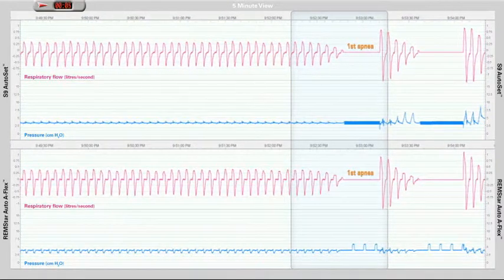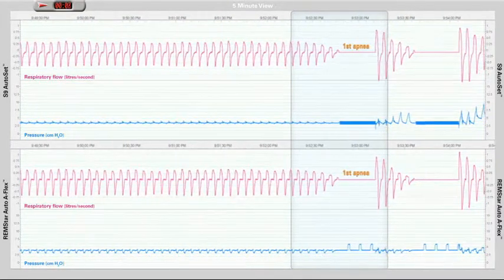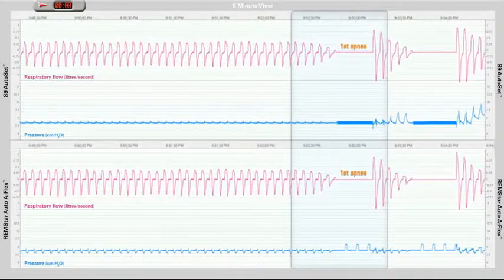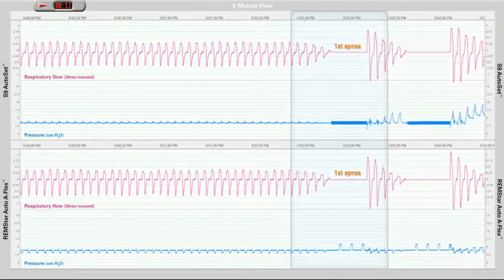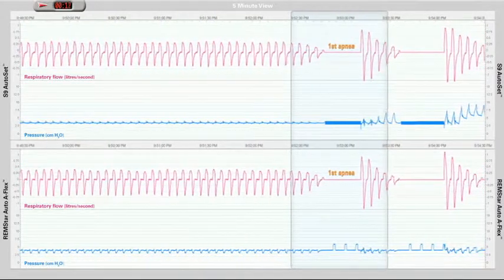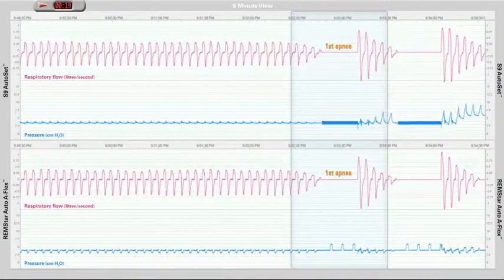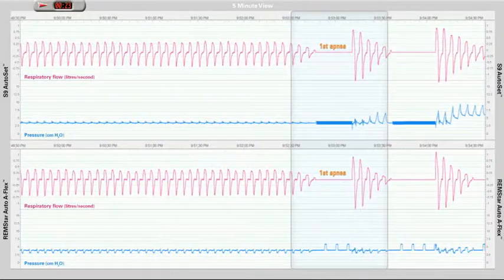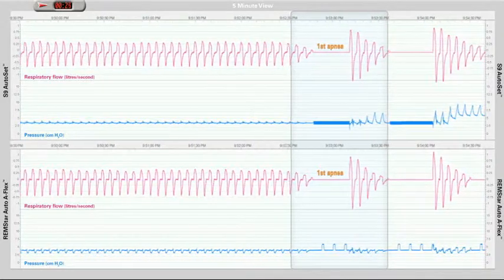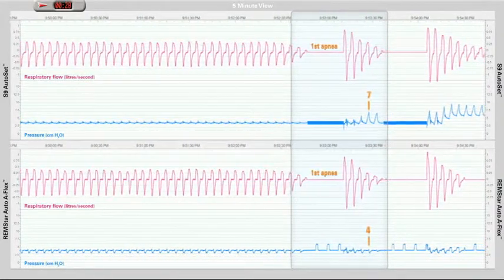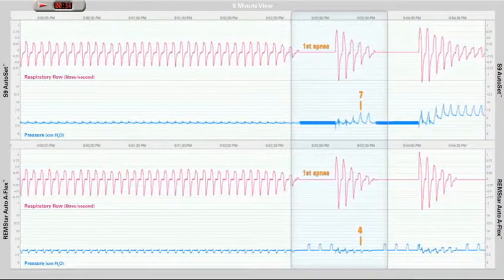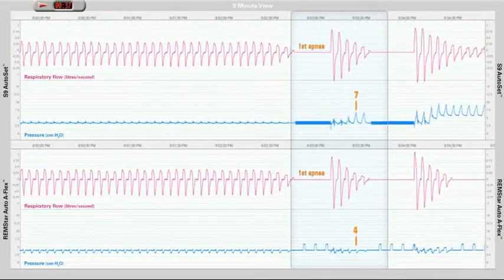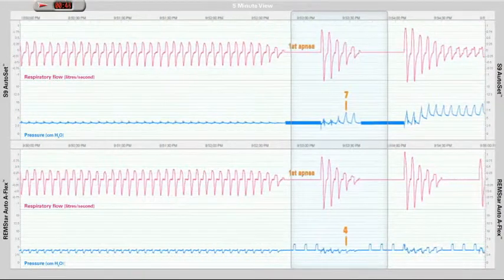The S9 Autoset detects that the apnea is obstructive and responds by increasing the treatment pressure by approximately 3 cm to 7 cm. The Remstar Auto detects that the first apnea is obstructive, yet shows no response to this first apnea.